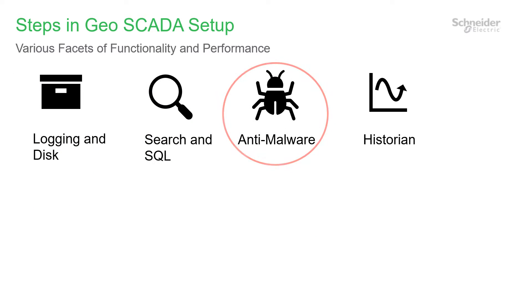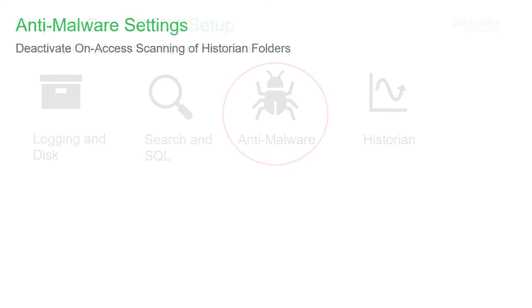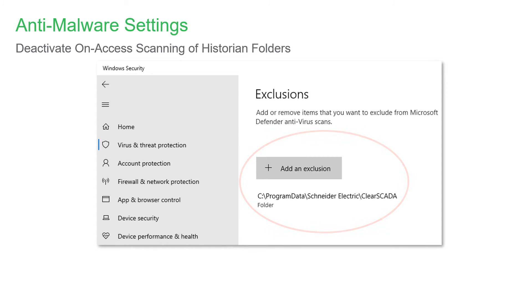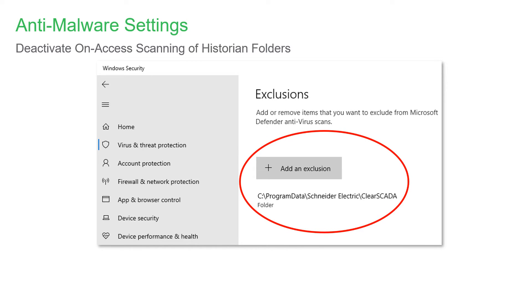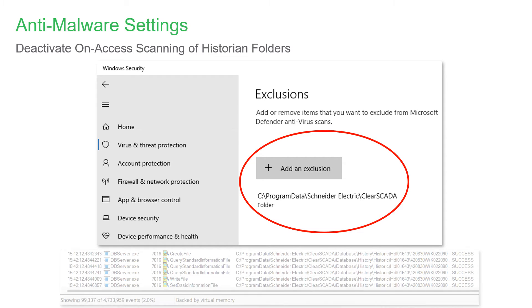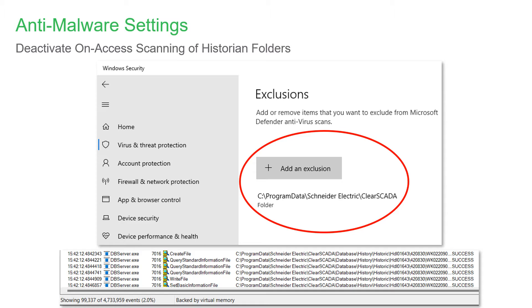In this case I'll mention some practices related to anti-malware setup. Of course we want the best security arrangements for SCADA and that includes using anti-malware software. However this can interfere with system performance. So while we can't offer settings for specific products, we do recommend turning off on-access scanning for the SCADA database folder, particularly the historian folders. If your anti-malware software supports it you can leave a scheduled scan running for these folders, providing that such a scan does not lock a file preventing change, which could cause the SCADA database to pause. You can check which programs are accessing files using the Sysinternals Process Monitor tool available from Microsoft.